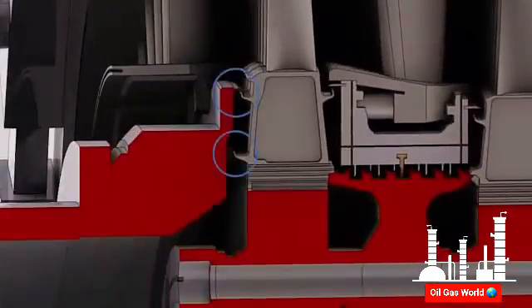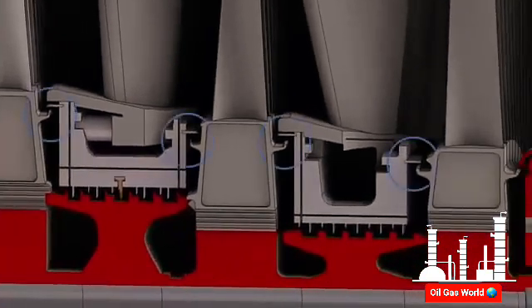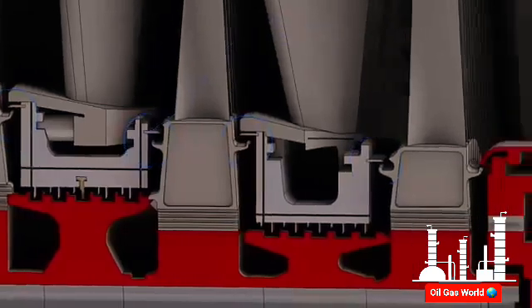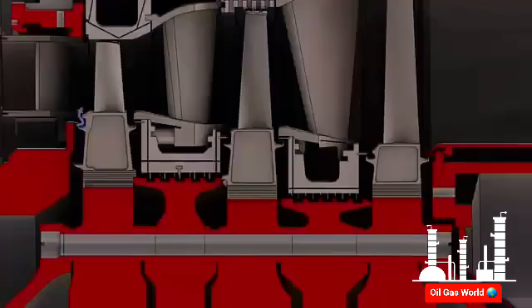Seals from the first stage nozzle support ring mate with sealing wings extending from the forward side of the first stage bucket shank. Also, seals from both sides of each diaphragm mate with sealing wings from both sides of each bucket. The seal from the exhaust frame mates with the sealing wing on the aft side of the third stage bucket shank at the forward end of the inner barrel.